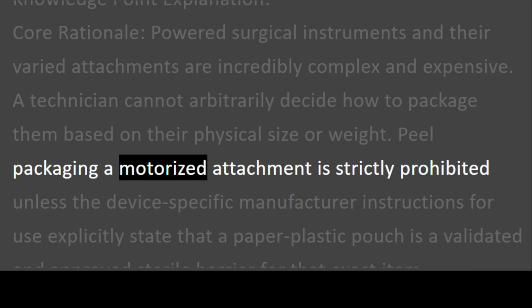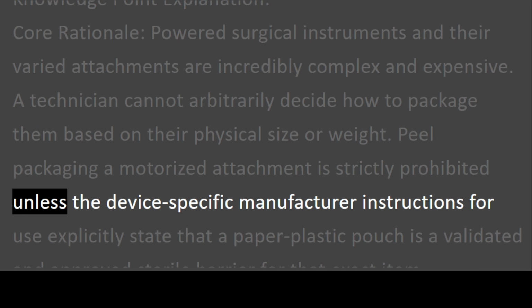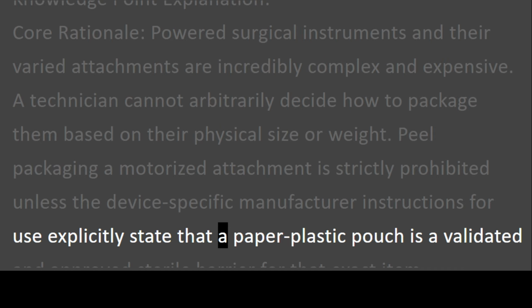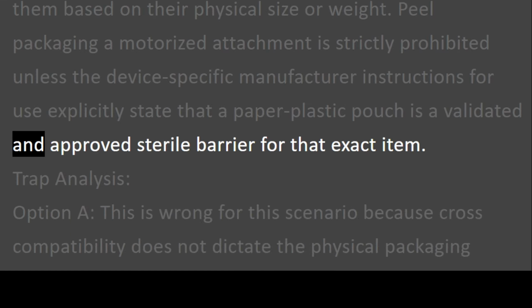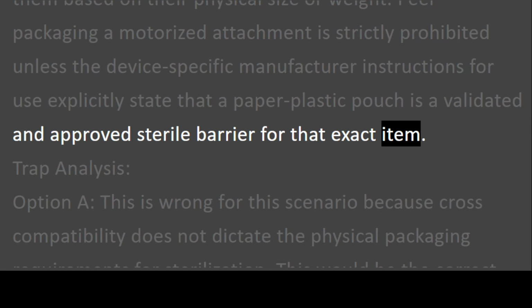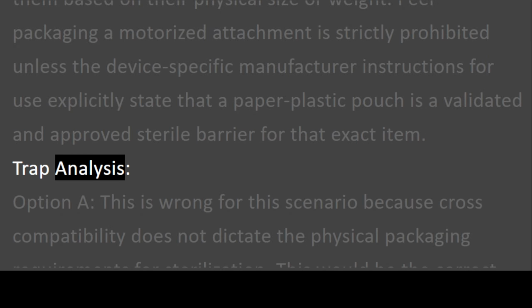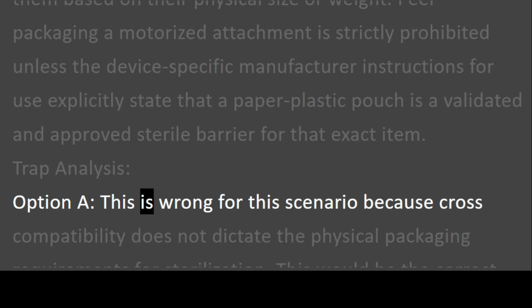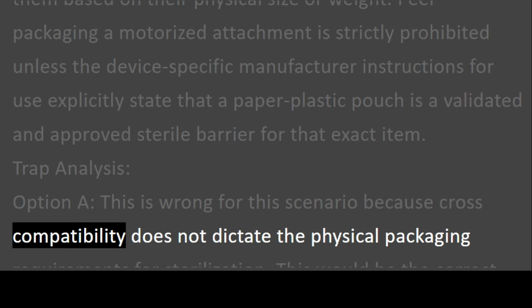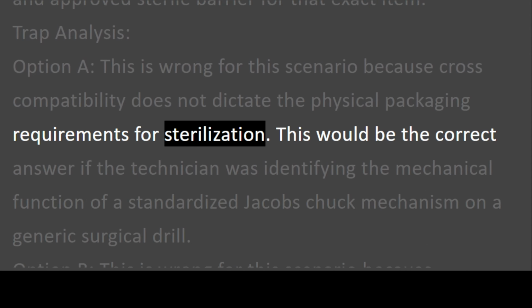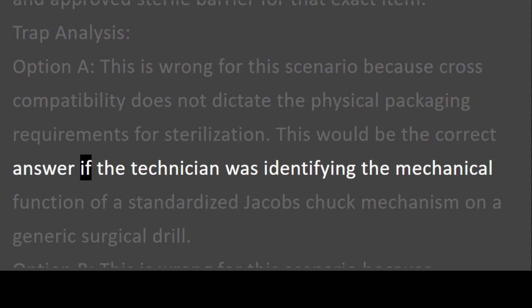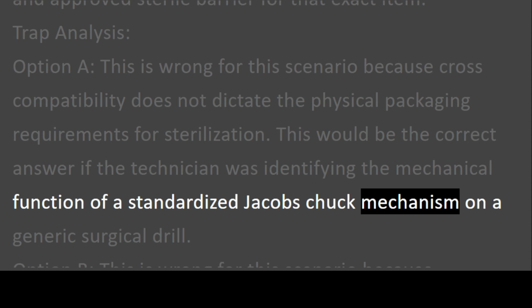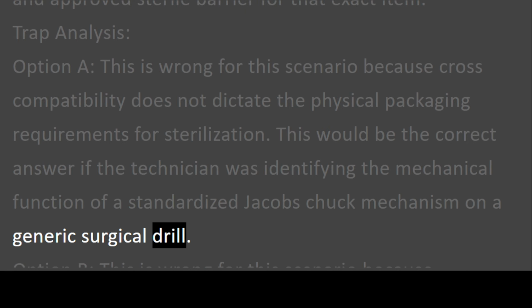Peel packaging a motorized attachment is strictly prohibited unless the device-specific manufacturer instructions for use explicitly state that a paper plastic pouch is a validated and approved sterile barrier for that exact item. Trap analysis. Option A. This is wrong for this scenario because cross-compatibility does not dictate the physical packaging requirements for sterilization. This would be the correct answer if the technician was identifying the mechanical function of a standardized Jacobs chuck mechanism on a generic surgical drill.